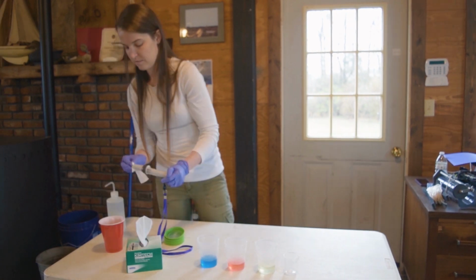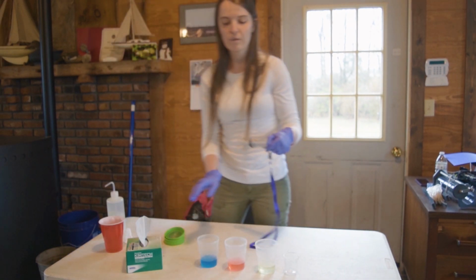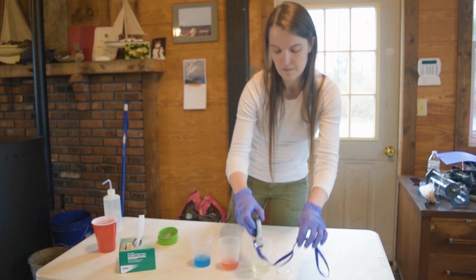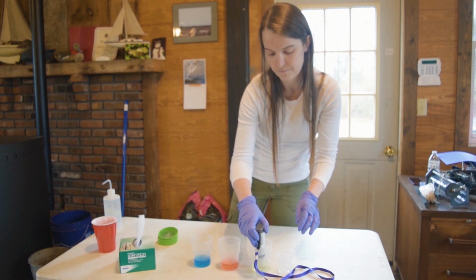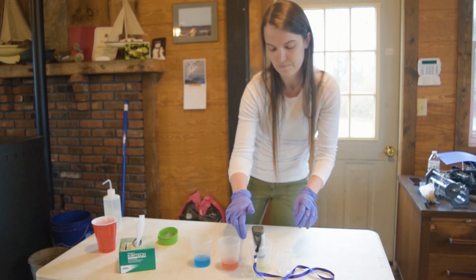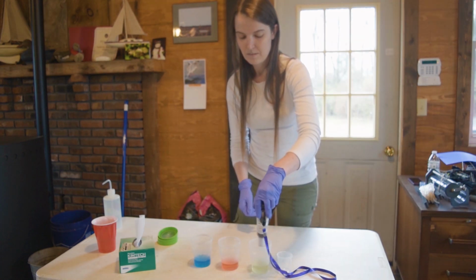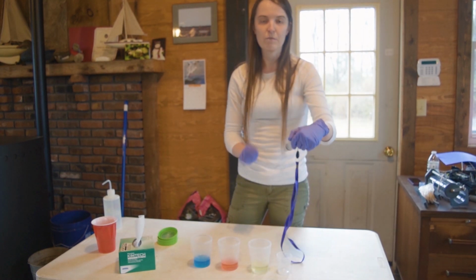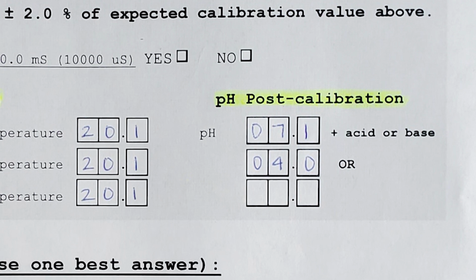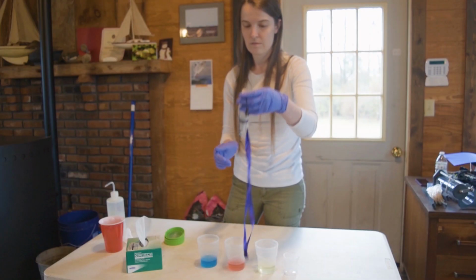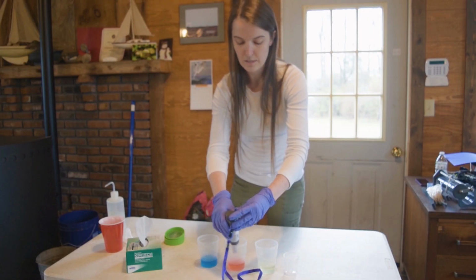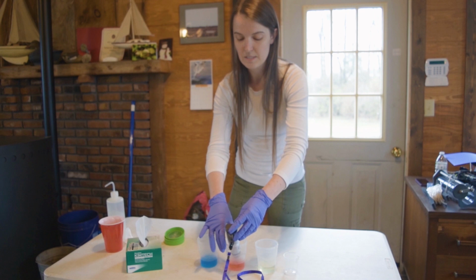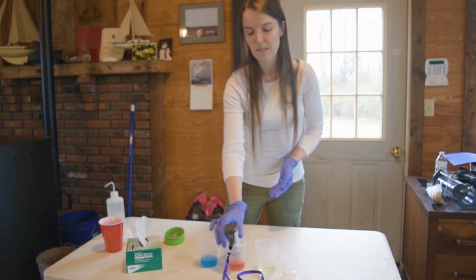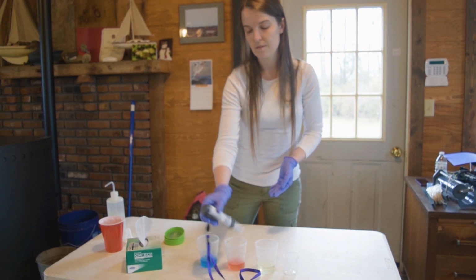Use the 7 solution first. Rinse and dry the probe, turn on the meter, then insert and swirl in the 7 solution. Wait for the value to stabilize and record this value on the site sample datasheet in the pH post-calibration column. Repeat this process with either the 4 or the 10 solution. Dispose of the pH solutions at your home in the drain.